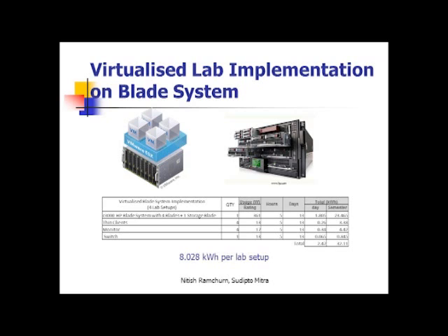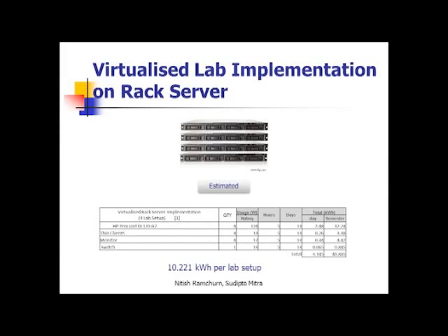And on this setup, we consume around 8 kilowatt hour, which is considerably lower than the non-virtualized lab on the blade server. Finally, we compared the virtualized blade implementation with the equivalent rack mounted server implementation, and the estimated power consumption for the rack mounted servers is 10.2 kilowatt hour.